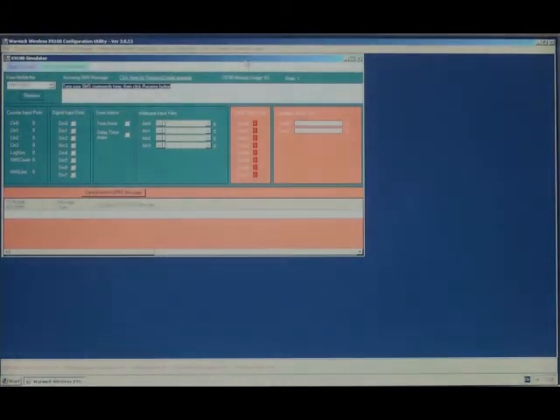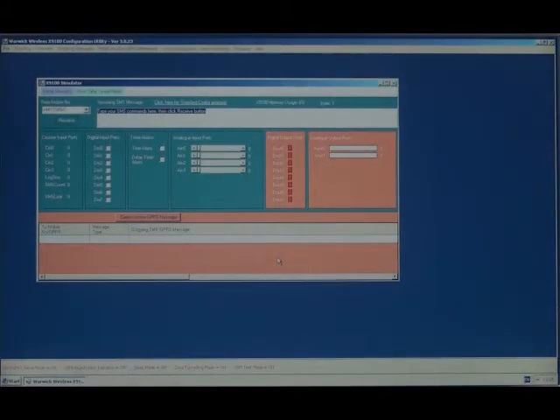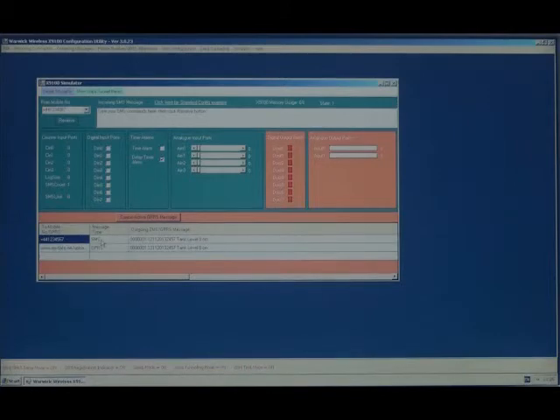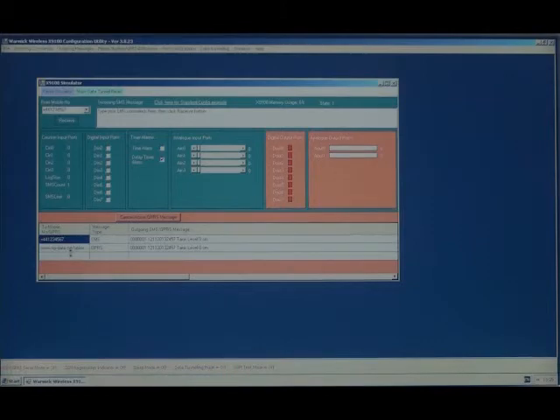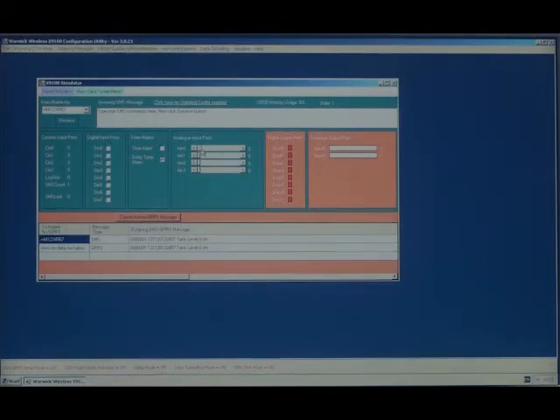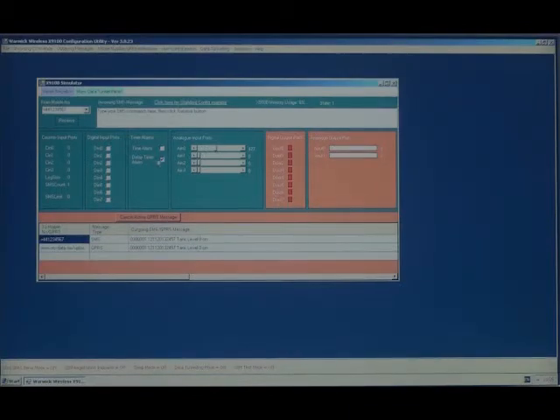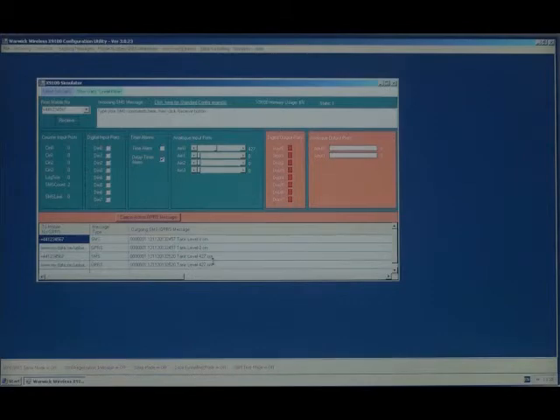We can now test whether our configuration has been successful by opening the simulator. All the parameters of the X9100 can be tested here. So if we click on Delay Time Alarm, we can see that both messages are sent. One by SMS to a mobile phone, the second by GPRS to the MyData website. If you grab hold of the analog slider for A in 0 and click on again, we can see that the level has changed from 0 to 427 cm.